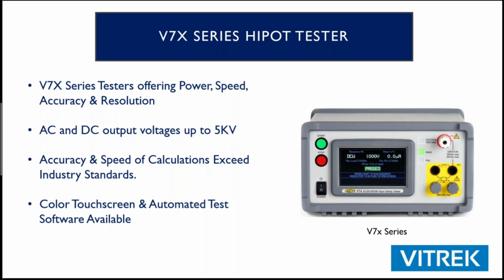One of the biggest issues you can have with a high voltage product is to have a forced air product that kind of gets everything gummy and dirty inside the unit and really can affect our performance over time. It's important that you keep these things clean on the inside. V7X does not have that issue at all. It's going to output 5 kV AC and DC, which is more than enough for any of the segments here. It's a very fast and accurate and reliable tester.